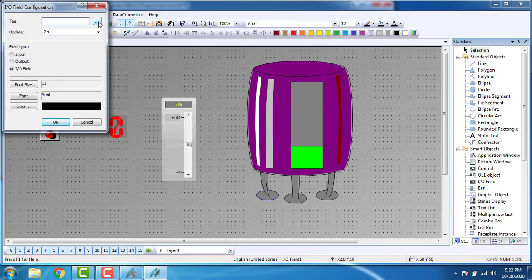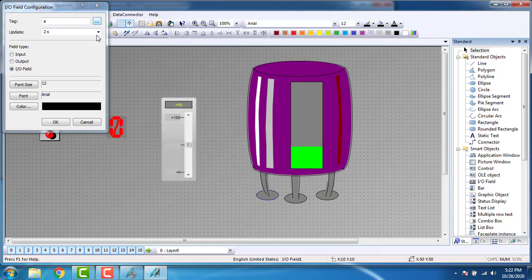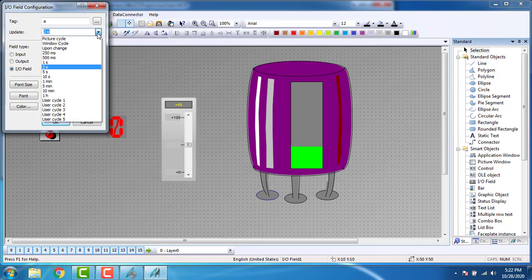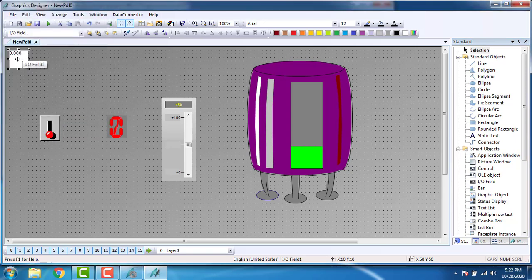Our tag will be analog. Go to Tags and this is my analog tag 'A' — I have previously defined it in the tag management. Click A and OK. The update cycle will be 'Upon Change' — on every change, that analog tag should be displayed or updated. Go to the field type, which is output — I need it to only show the output. Go to output and click OK. This is my IO field.